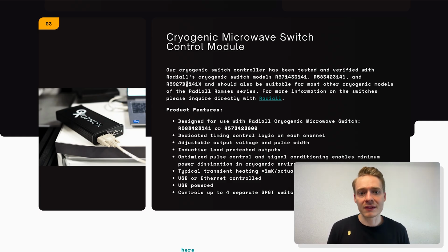Product features designed for use with Radiall cryogenic microwave switch, which is one of the most common cryogenic microwave switches in the field. Then dedicated timing control logic on each channel, adjustable output voltage and pulse width, inductive load protected outputs, and optimized pulse control and signal conditioning enables minimum power dissipation in a cryogenic environment.